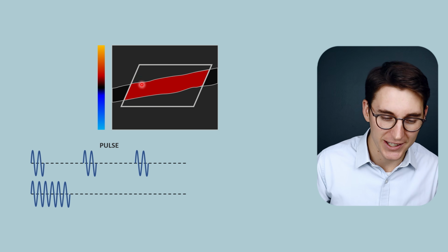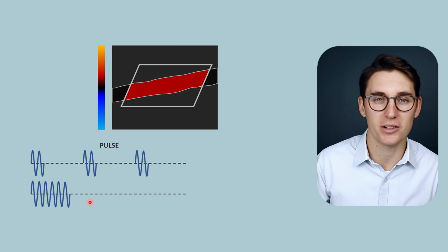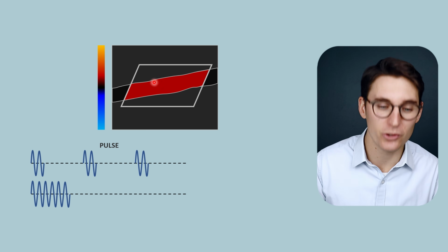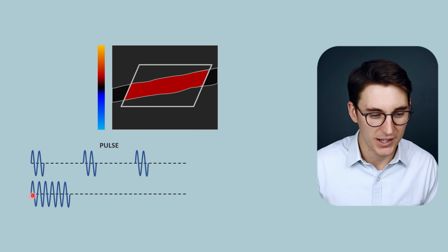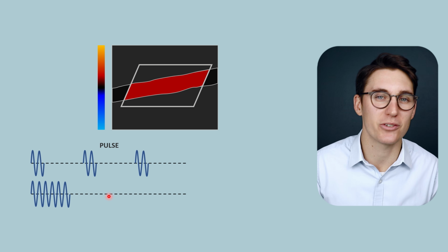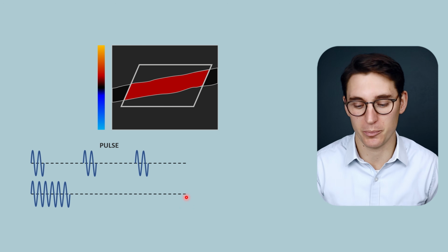Within the active area, in the color Doppler mode area, what we need to do is increase our spatial pulse length a bit. We need to narrow that bandwidth down in order to get good frequency data coming back. Now because we've increased our spatial pulse length and we still need to wait for those echoes to return, what we've done is we've increased our pulse repetition period.